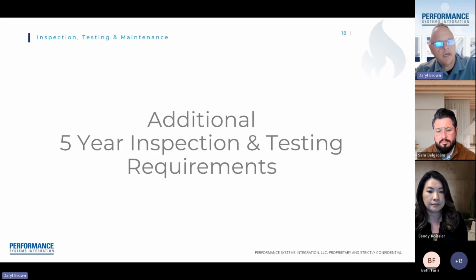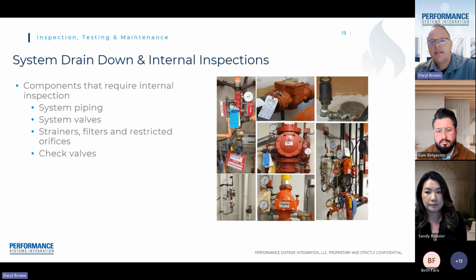Another item here in California, and it's actually required throughout the United States, but especially here in California, it's strongly enforced, is the 5-year inspection and test requirements. Basically, the 5-year is an additional scope of work that's done every 5th year. So this is performed in addition to all the annual and quarterly inspection items that we do. Every 5th year, we have to do some extra items as required by NFPA 25 and our local fire jurisdictions.